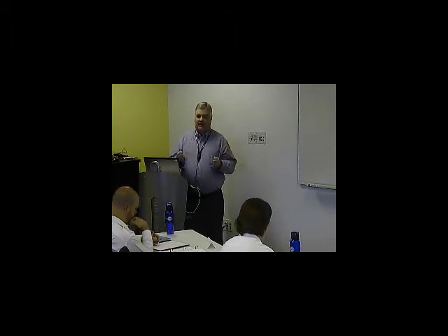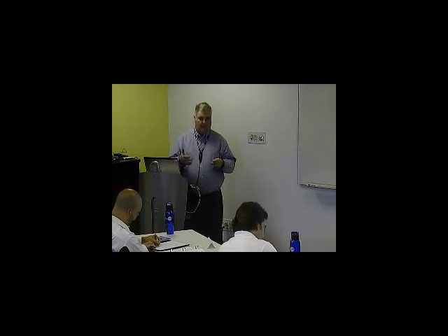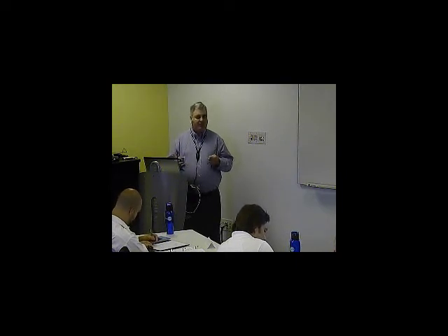Now here's one that's not on the slides. A low voltage device. Low voltage. As compared to an ICD, which is a high voltage device. So you may hear people refer to the pacemaker or the implanted pulse generator as a low voltage device.